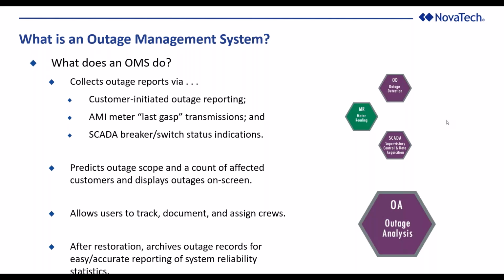And lastly, for the purposes of SCADA, it can send breaker, switch, and recloser status indications that provide data to an OMS. The OMS then takes that data and predicts an outage, including the scope or size of the outage and the count of affected customers, and displays information about those outages on the screen in the software.